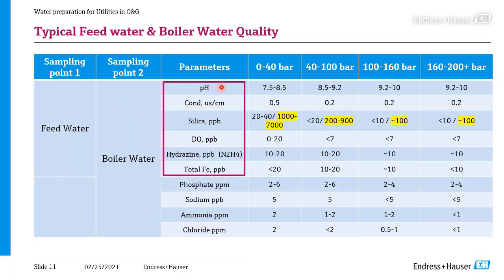Here for boiler feed water, for steam generation in refineries, where power generation is also included, you have a pH range, conductivity, silica in ppb, so parts per billion, on a very low range. Dissolved oxygen has to be kept at a very low level. As I said, under high pressure and high temperature, oxygen becomes very corrosive. To remove oxygen, hydrazine is used. In the past, and in some countries it's still used. Nowadays there are also other substances to do the deaeration, to remove oxygen from the water. And same here for the other parameters. So here we need to make sure that we stay below these limits.